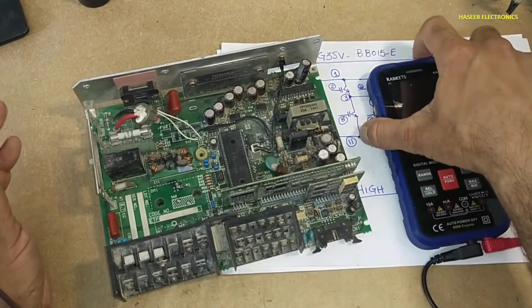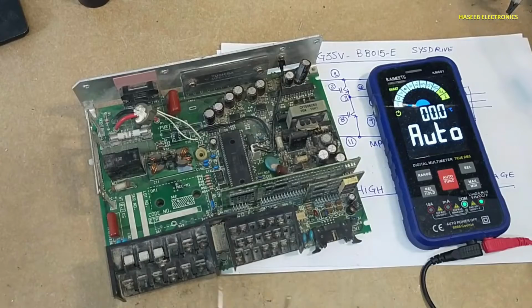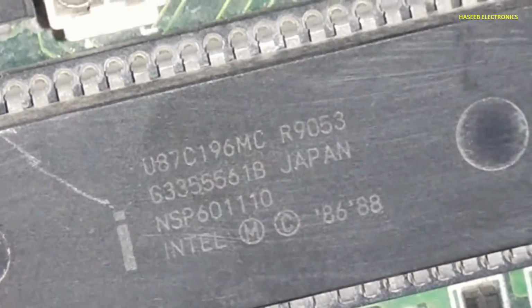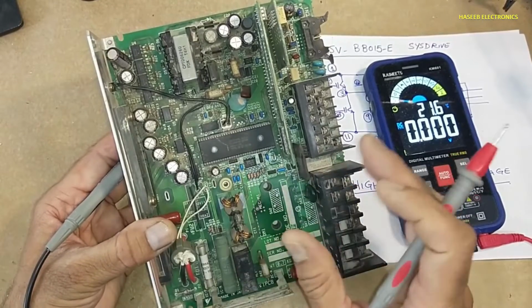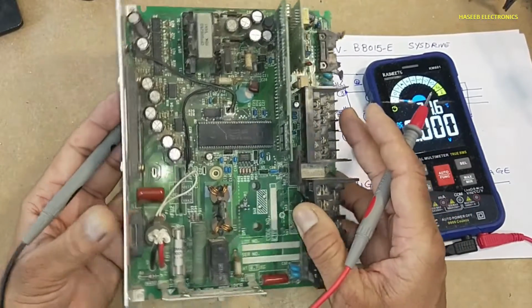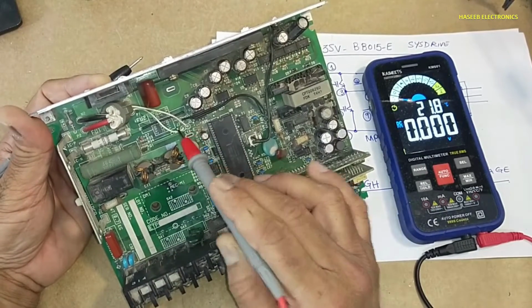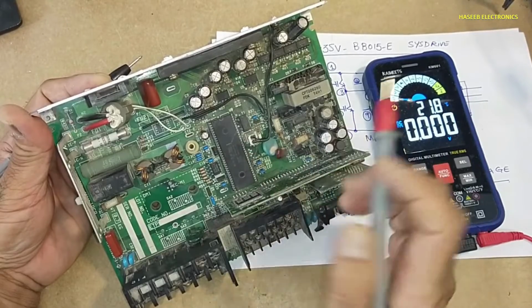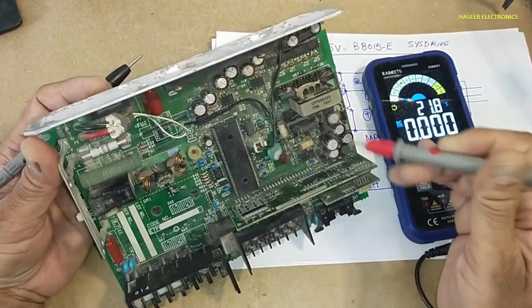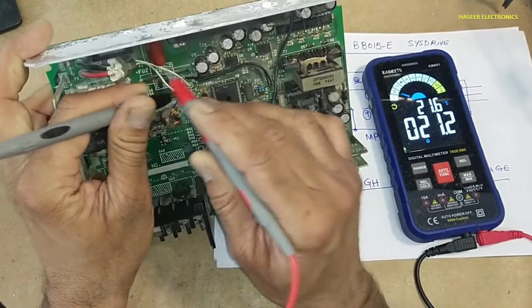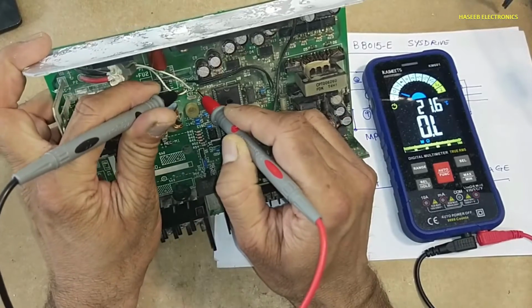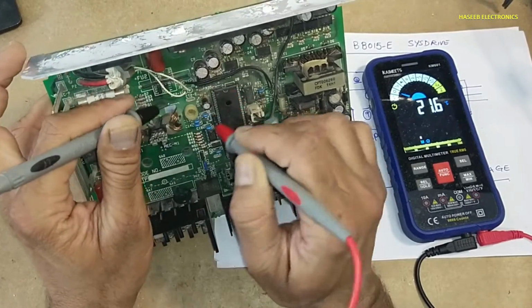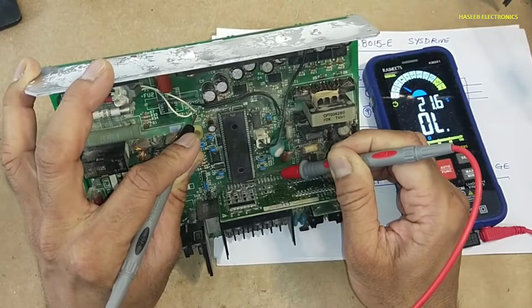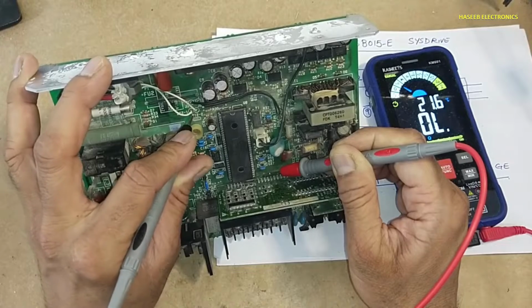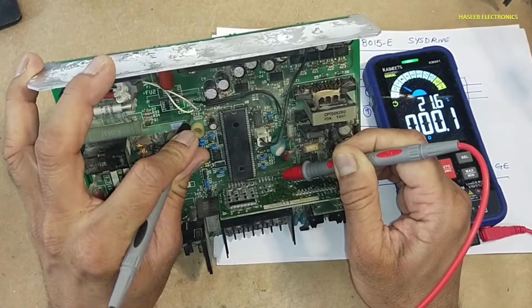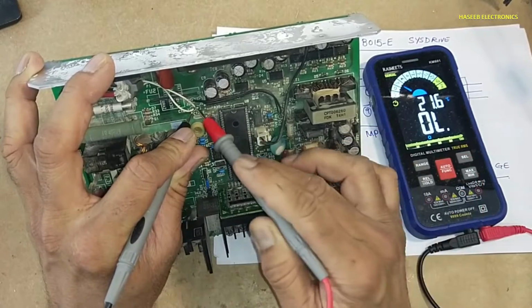will reach the analog to digital converter card. It is a sampling card because it is using here the 80C196. This Intel microprocessor is specially designed to control motors. It cannot understand the voltage value. It needs digital data. So this voltage value will reach this card. This winding has 21 ohms resistance. Then this line is reaching this pin, and this line is reaching this pin. On these two pins, both signals, high and low, are reaching here.